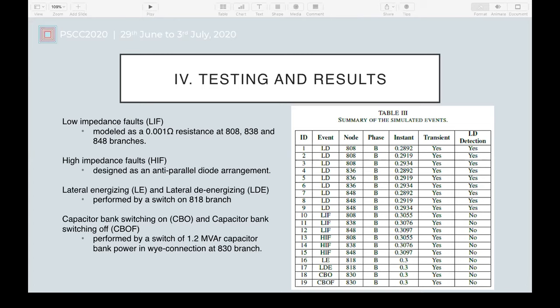Some events were simulated to test the efficiency of the detection scheme to distinguish lightning strikes from other events, such as low impedance faults modeled as resistance at three branches, high impedance faults designed as an anti-parallel diode arrangement, lateral energizing, and de-energizing performed by a switch on the 818 branch, and capacitor bank switching on and off at the 830 branch. In Table 3, there is a summary of the simulated events characterizing their results by node, phase, instant, transient occurrence, and lightning discharge detection.